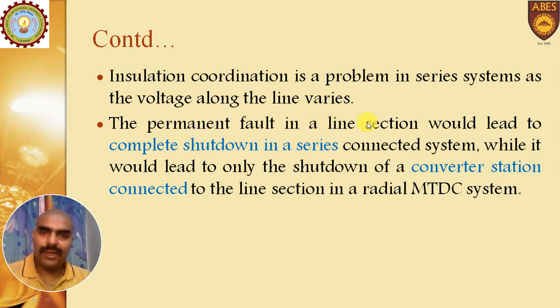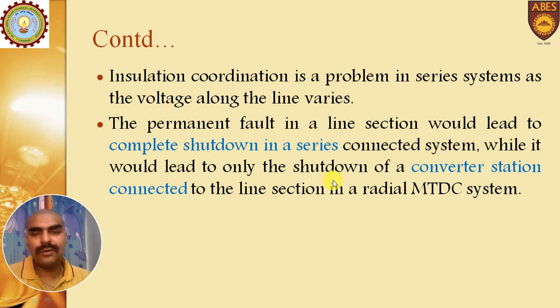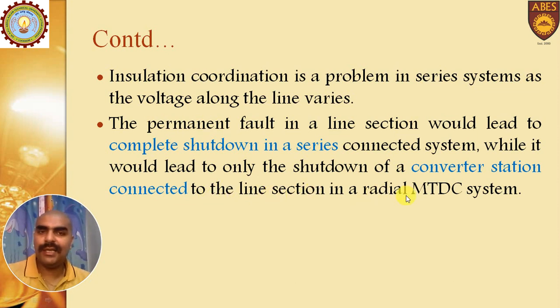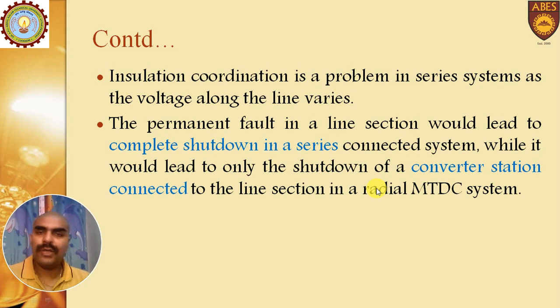A permanent fault in a line section would lead to complete shutdown in a series system, because all lines are connected in series. In contrast, in a parallel MTDC system, it would lead only to the shutdown of the converter station connected to the faulted line section in a radial MTDC system. So in series, all lines will be affected through that particular fault.